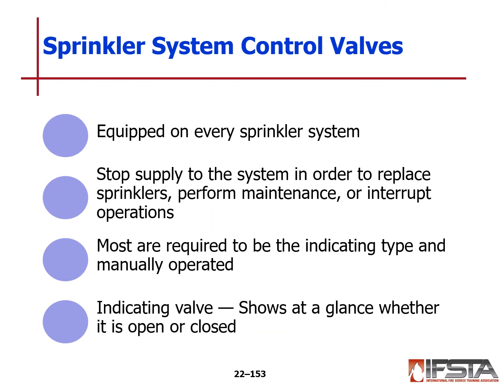System control valves are equipped on every sprinkler system. Basically, they stop the supply to the system in order to replace sprinklers, perform any maintenance, or interrupt operations if necessary. Most are required to be the indicating type and manually operated. So it tells you it's open, it tells you that it is closed. This indicating valve, again, at a glance, shows the words open or closed.